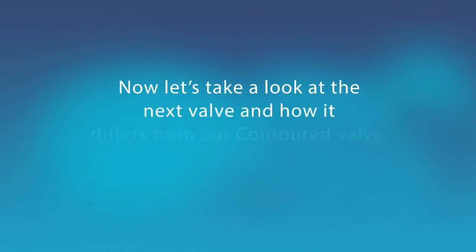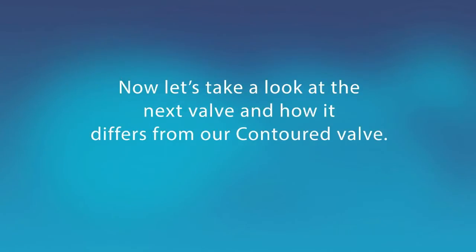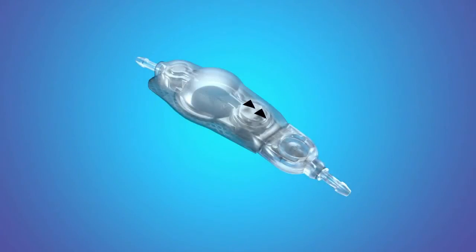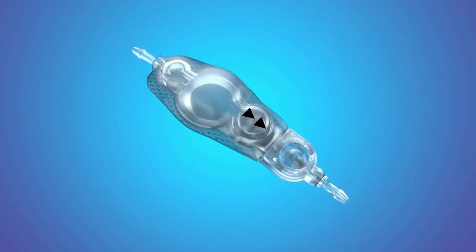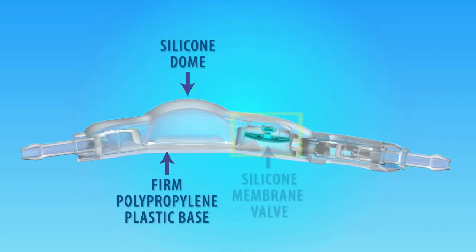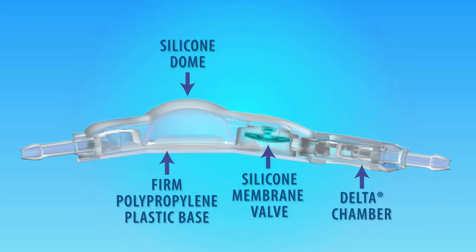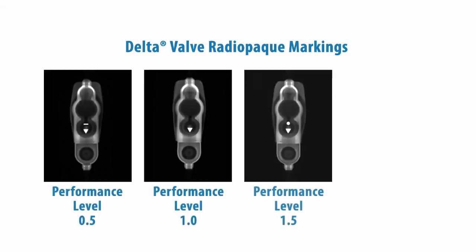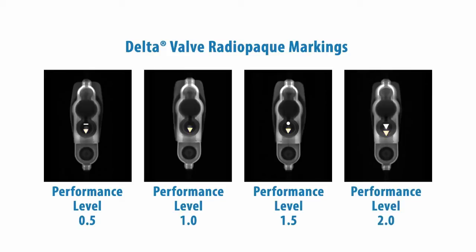Now let's take a look at the next valve and how it differs from our contoured valve. The Medtronic Delta Valve consists of a firm polypropylene plastic base, a silicone dome, a silicone membrane valve, and unlike the contoured valve, it has a distal delta chamber component which provides siphon control when the patient is in an upright position. The Delta Valve also has proximal and distal occluders for selective flushing. Like the contoured valve, the Delta Valve has radiopaque markings; the arrow indicates direction of flow and the marking behind the arrow indicates the valve performance level.